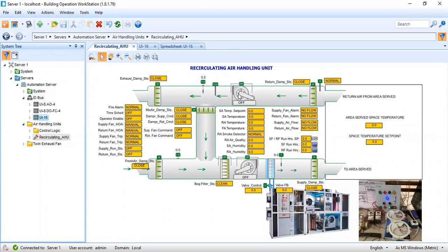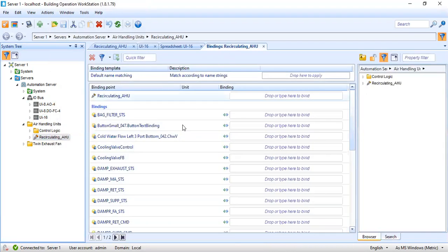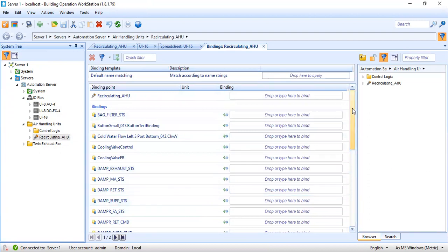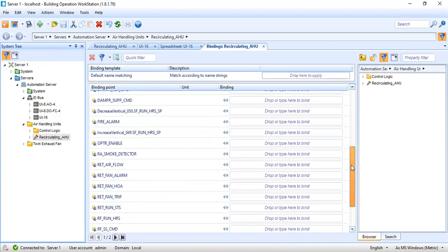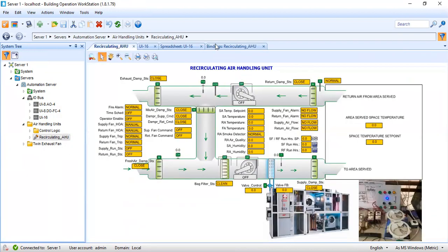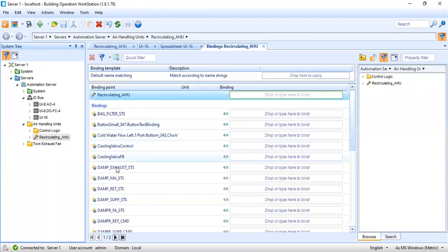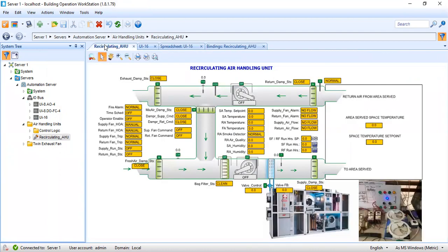Let's start doing the binding. As you can see, the points are not yet binded. If the mouse pointer changes to a pointing finger, meaning the point or object is already binded to the physical points where it will get the real-time values. Since I defined this already, let me try to do the actual bindings. You will go to Edit Bindings. This is my edit binding window. It will display all the object points — so many points as you can see in the graphics. Our concern for this first part is to bind the physical points of the fans.